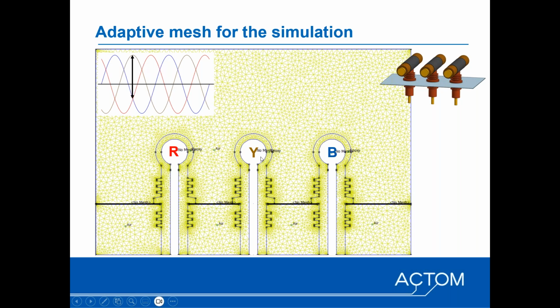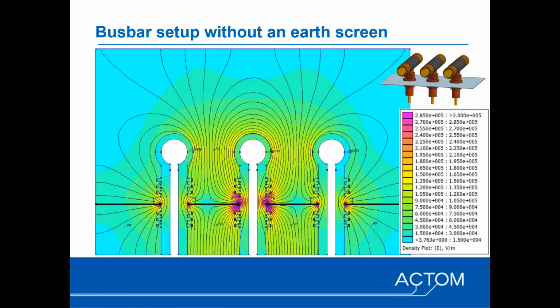The voltage being applied at any moment of time is effectively the 3-phase system, where we've got the yellow phase, for instance, on the peak, and the red and the blue phase would then be at a negative voltage relative to the earth potential. This plot shows the field plots without the earth screen being applied, and the important thing to note is that you've got a voltage distribution between the phases, and a voltage gradient from the live end up to where the earth potential is.